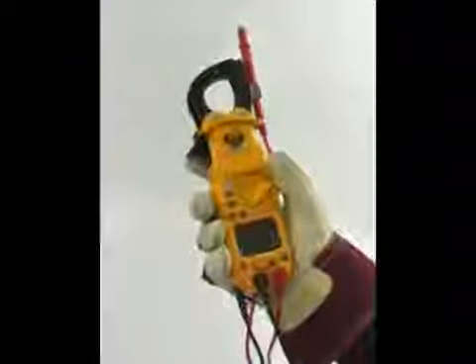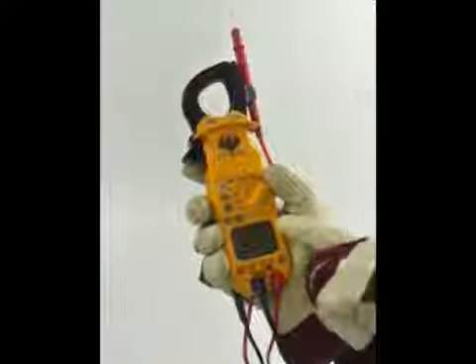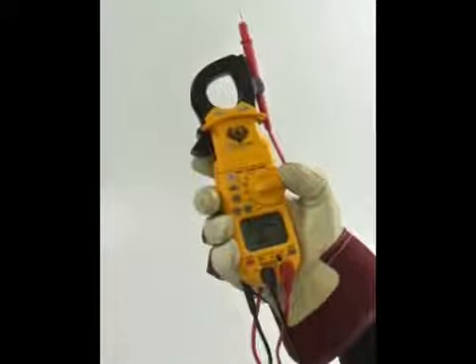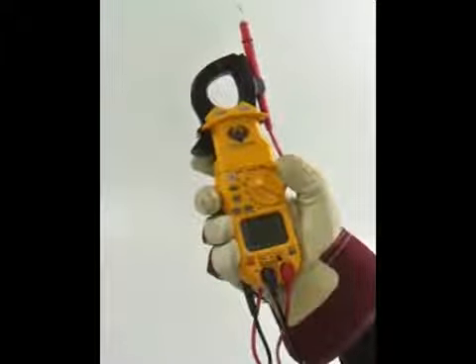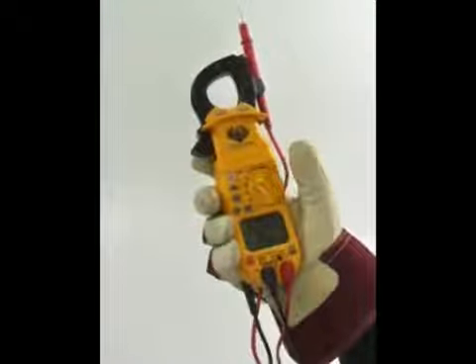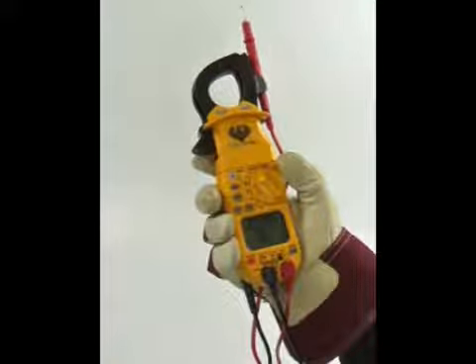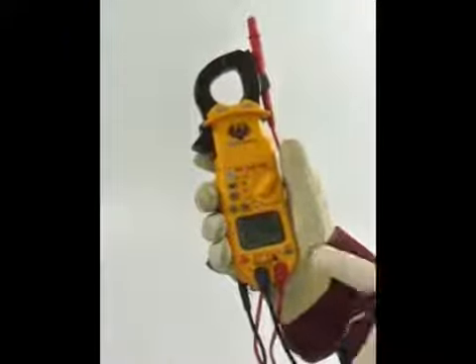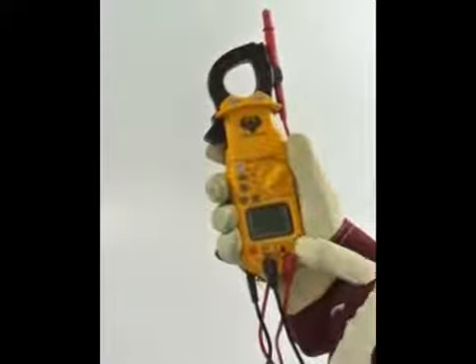Voltage up to 750 AC and 1000 volts DC, current to 400 amps AC, resistance to 40 megaohms, continuity and diode, capacitance to 4000 microfarads, 2000 microamps both AC and DC, and temperature ranging from negative 40 to 752 degrees Fahrenheit or negative 40 to 400 degrees Celsius. You can access frequency and duty cycle measurements by pressing the Hertz duty button when measuring AC volts or AC microamps.